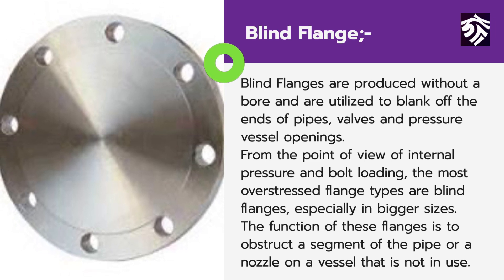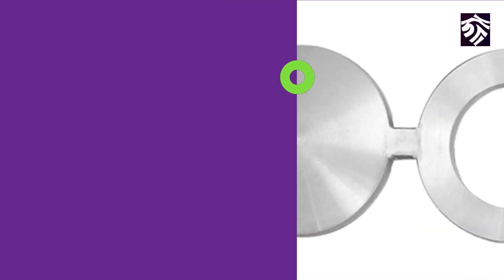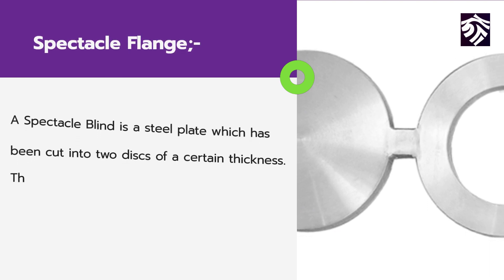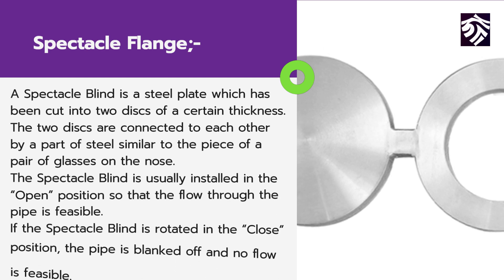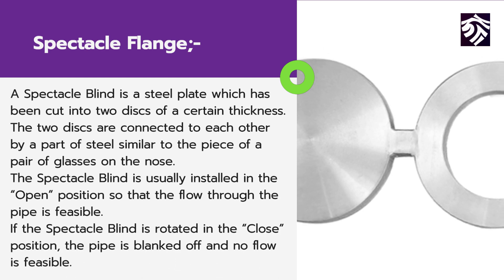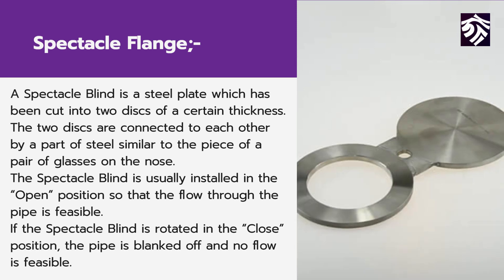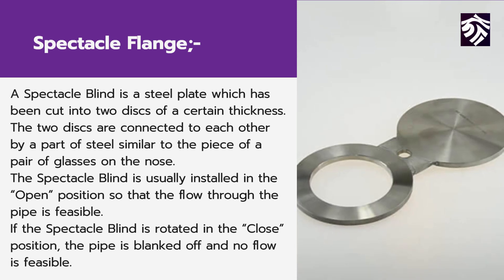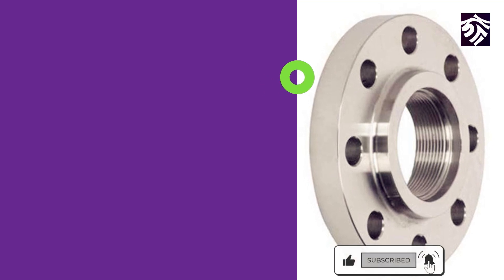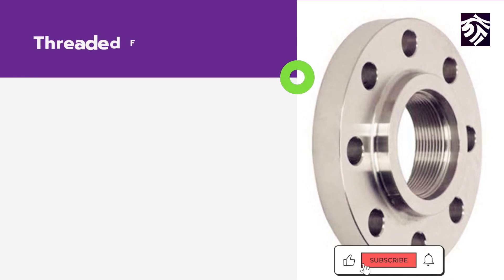Another very special type of flange is the spectacle flange. A spectacle blind is a steel plate which has been cut into two discs of a certain thickness. The two discs are connected to each other by a part of steel, similar to the piece of a pair of glasses on the nose. The spectacle blind is usually installed in the open position so that flow through the pipe is feasible. If the spectacle blind is rotated to the closed position, the pipe is blanked off and no flow is feasible.